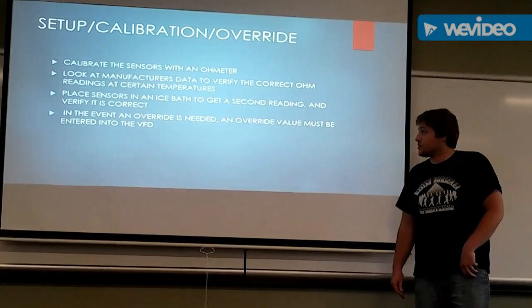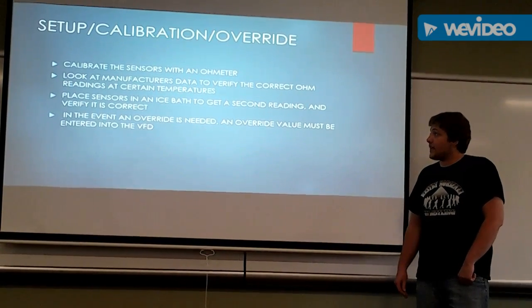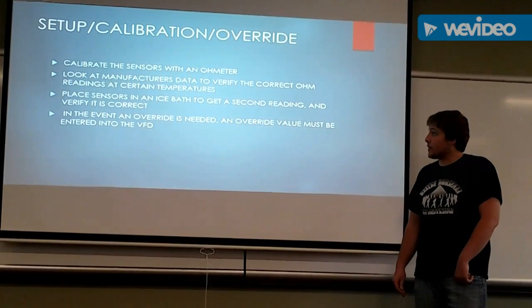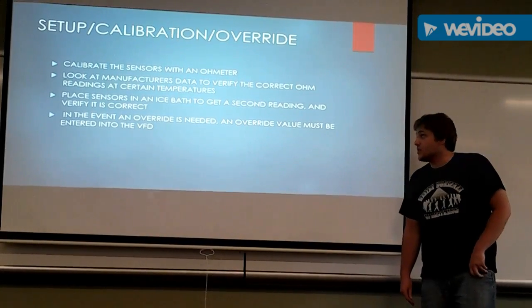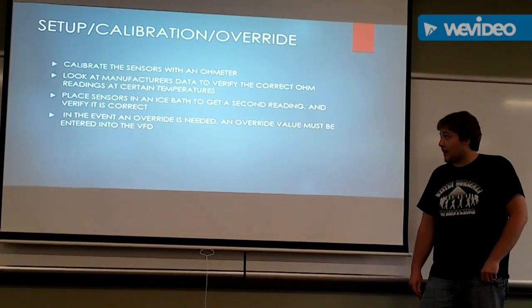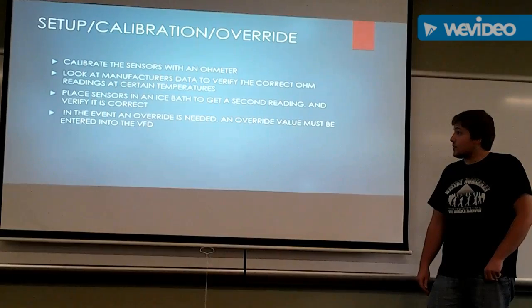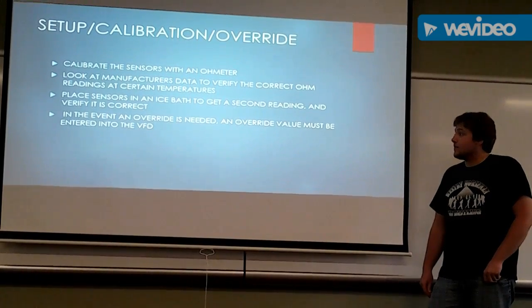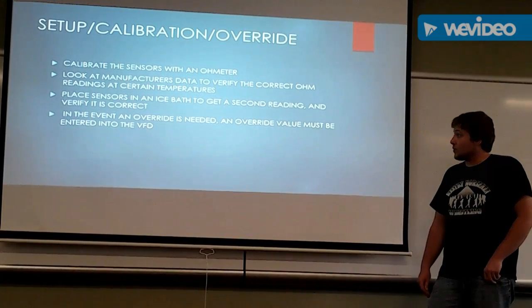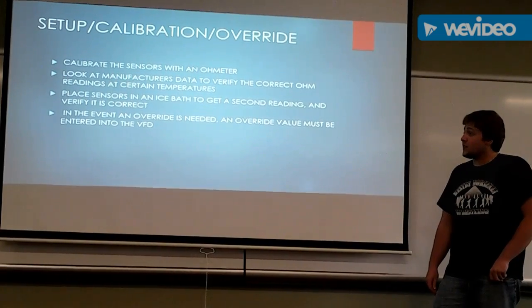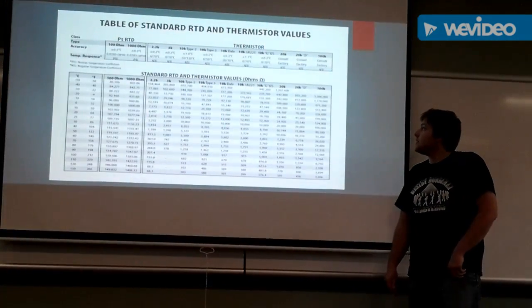Calibrate the sensors with an ohm meter. Look at the manufacturer's data to verify the correct ohm readings at certain temperatures. Place sensors in an ice bath to get a second reading and verify it is correct. In the event an override is needed, an override value must be entered into the VFD. This is the table.